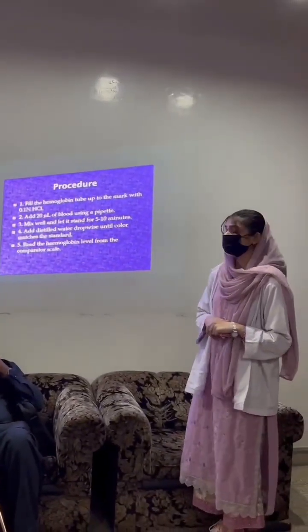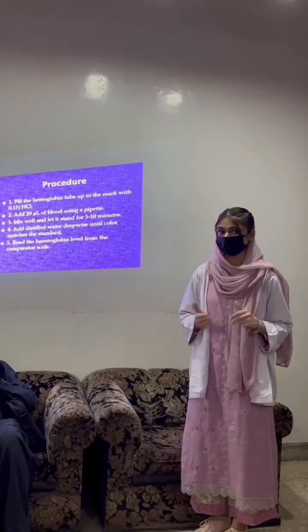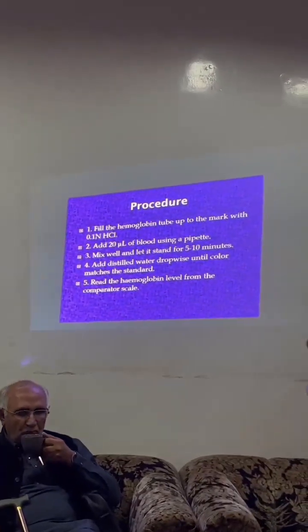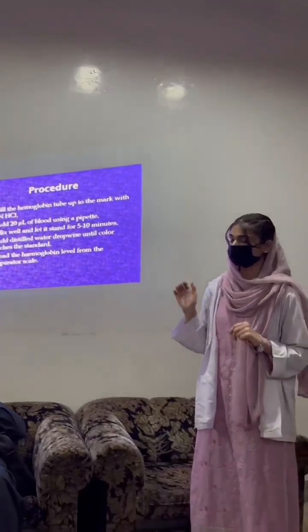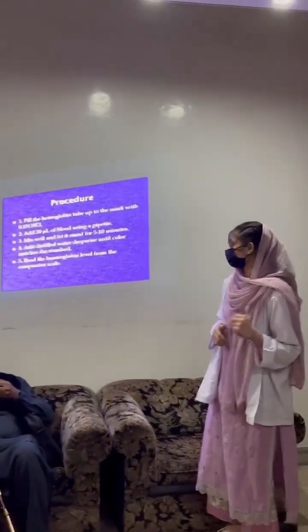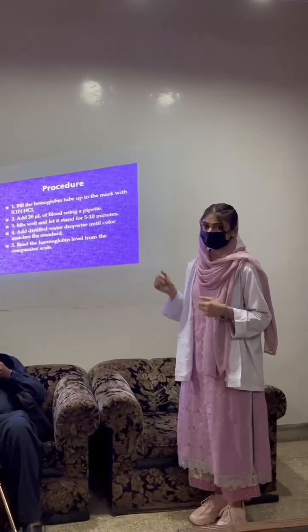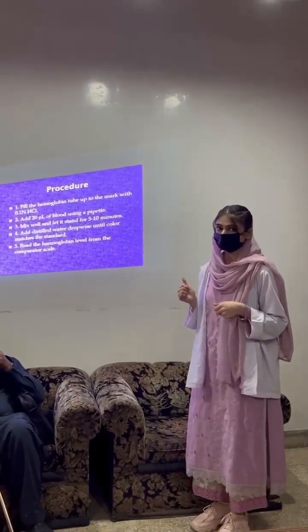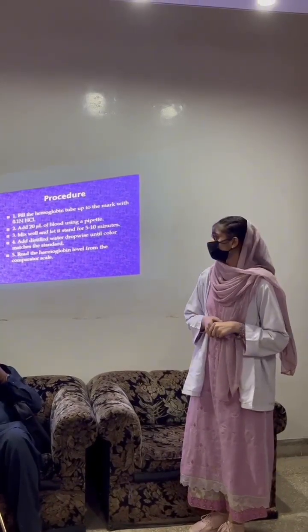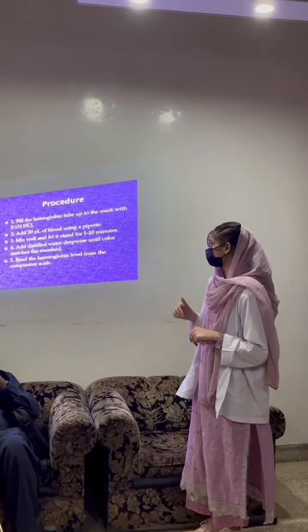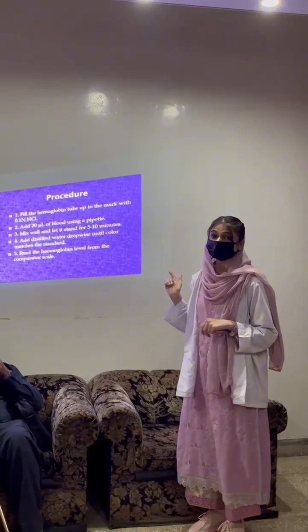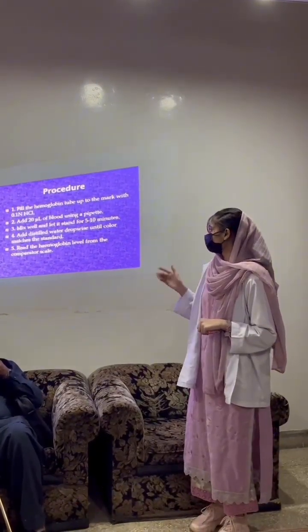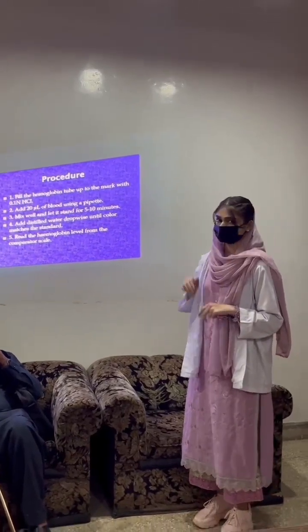Now the procedure — there are five steps. In the first step, fill the hemoglobin tube up to the mark with 0.1N HCl. In the second step, add 20 microlitres of blood using the pipette. In the third step, mix well and leave it to stand for 5 to 10 minutes. In the fourth step, add distilled water drop by drop until the color matches the standard. In the fifth step, read the hemoglobin level from the comparator scale.